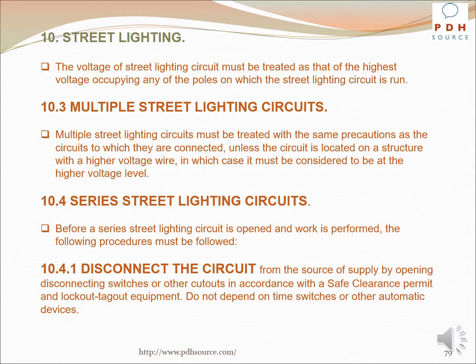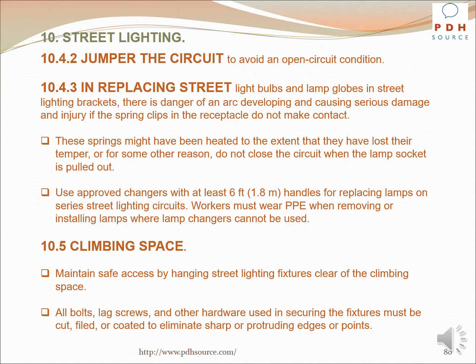Before a series street lighting circuit is opened and work is performed, the following procedures must be followed. Disconnect the circuit from the source of supply by opening disconnecting switches or other cutouts in accordance with a safe clearance permit and lockout tagout equipment. Do not depend on time switches or other automatic devices. Jumper the circuit to avoid an open circuit condition.